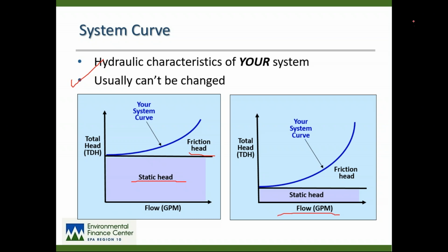This diagram on the right would be more like an irrigation system where you're not necessarily lifting the water very high up on a hillside. You might be pumping the water many miles through irrigation pipes over relatively flat land. So the system curve on a system like that would be a very steep curve. So as gallons per minute go up, the proportion of friction head to static head is actually much greater in a system like that, which does not have to lift water very high, but it may have to push water long distances at low elevations. So your system probably has a curve that falls somewhere in between these, and these obviously are not to scale, but I wanted to get you familiar with that term.